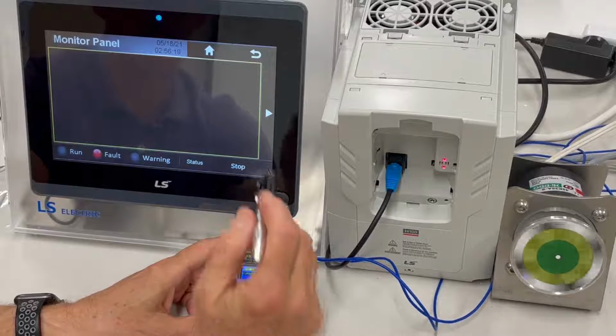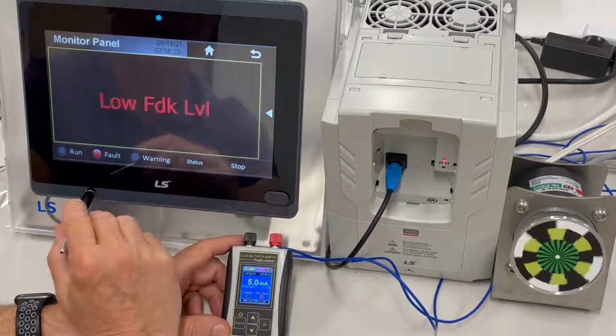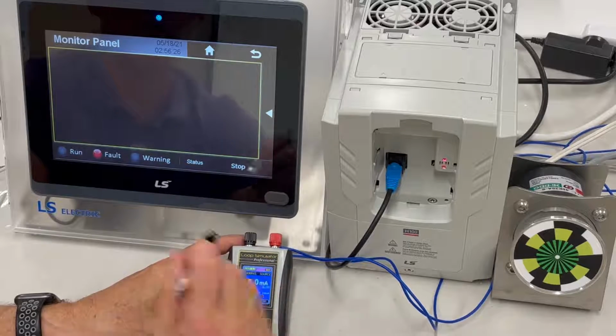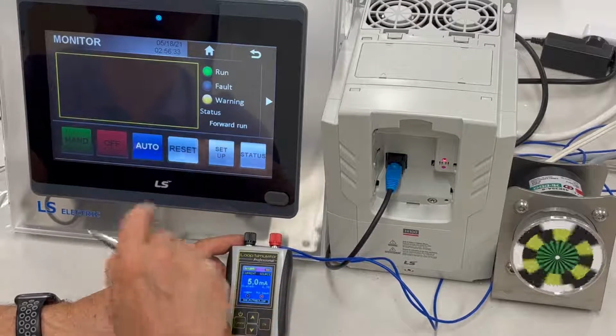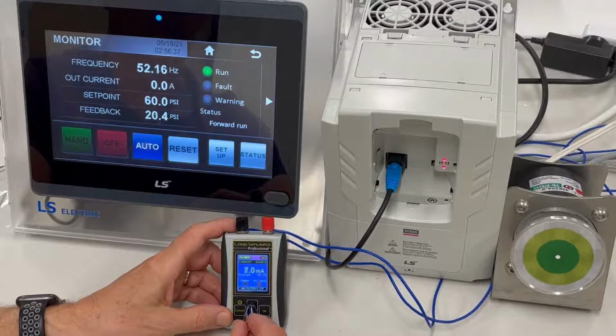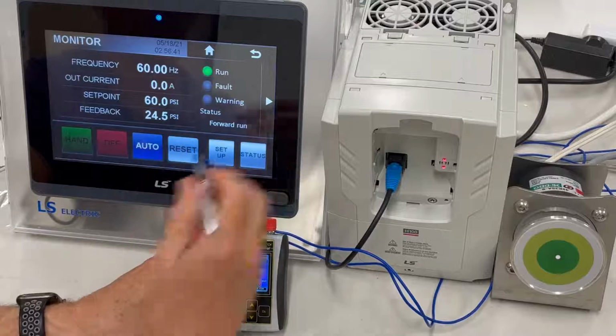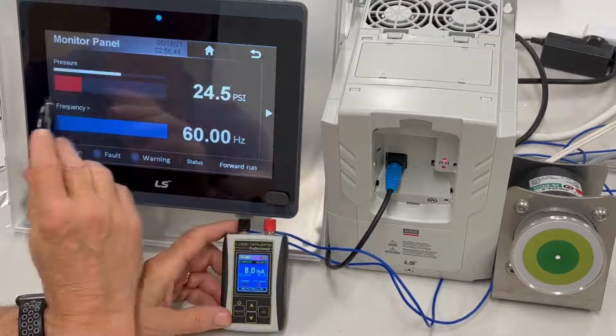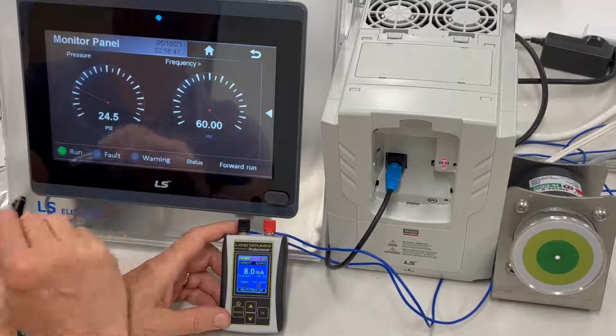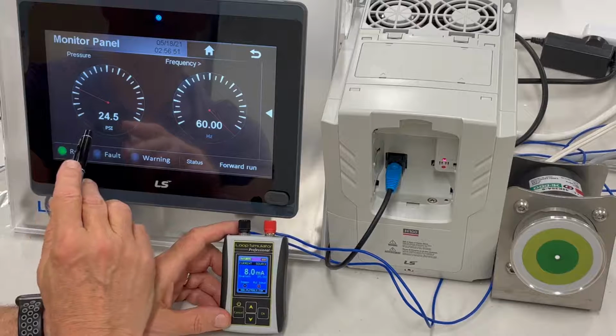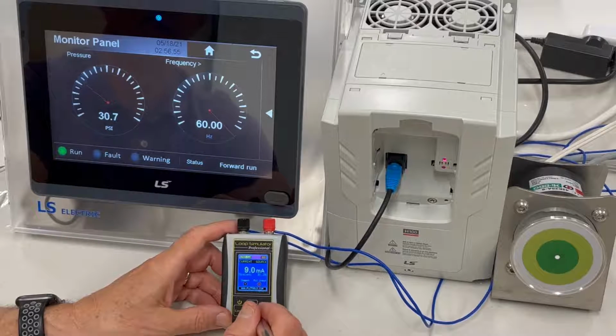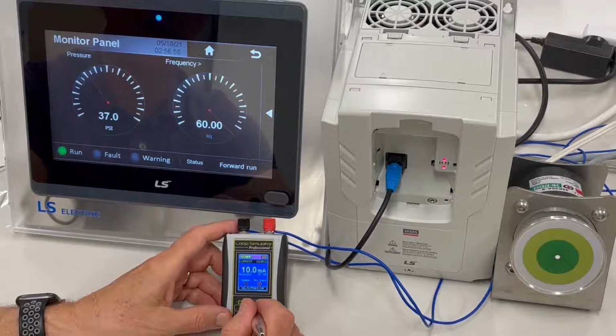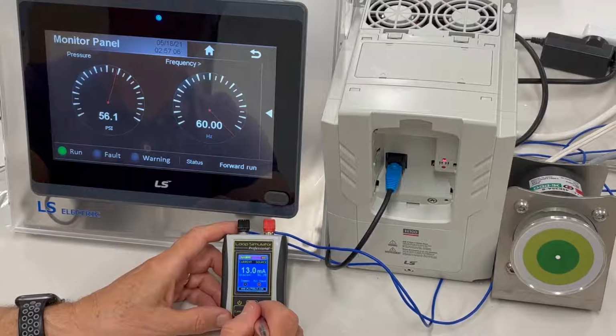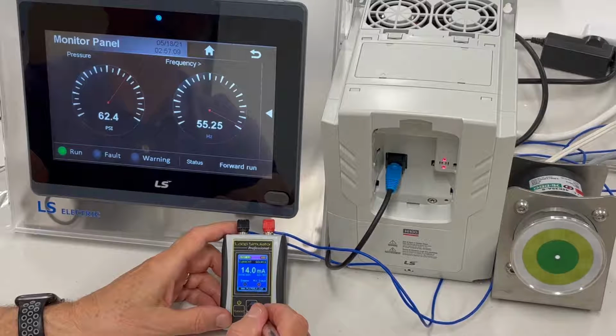So with that, there's different screens we can also show. So it is basically faulted out completely. So what we want to do is we'll go back to our home screen, and we'll hit a reset button here, and we go in auto. We fix the wire, so now we're going above, and the pump is operating normal. We also have a couple other screens here. Besides this bar graph that shows you this, if you wanted to look at a gauge system, we've added that to you. So you can see that the drive is at 60 Hertz, and this is our PSI rating. And if I change the transducer feedback, we can notice how it increments up on the PSI. A little different way of looking at it. So one more increment up on the PSI, and then we're going to go into sleep mode.